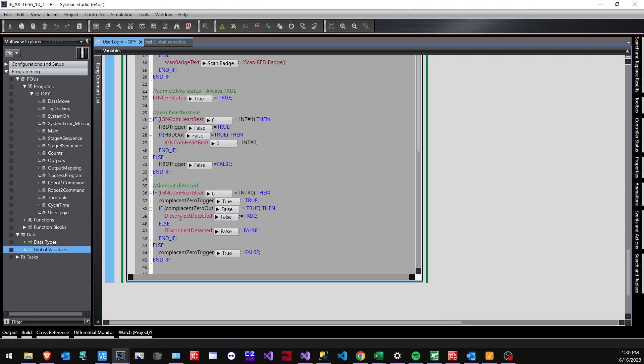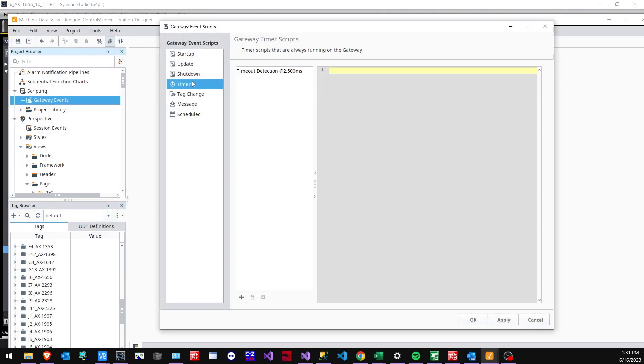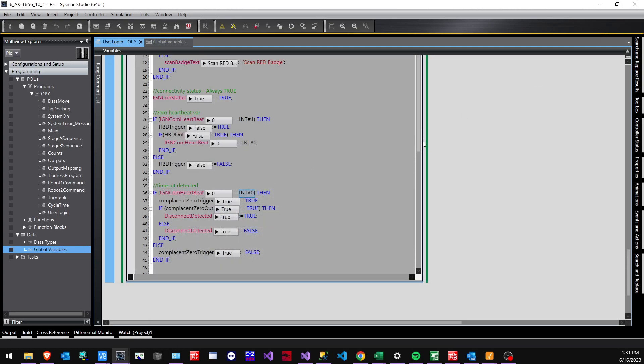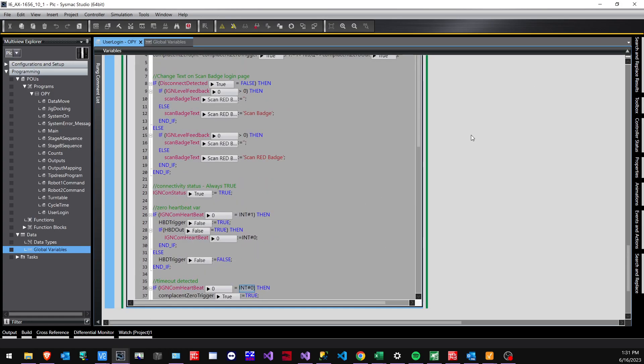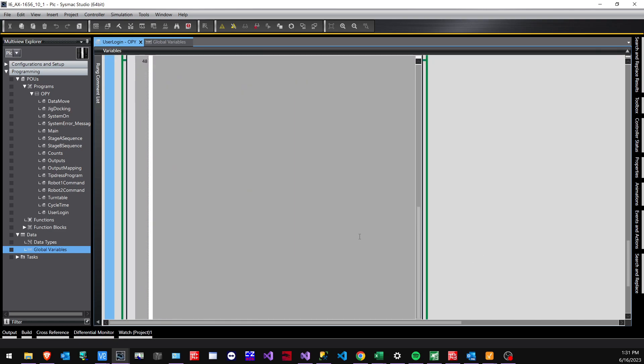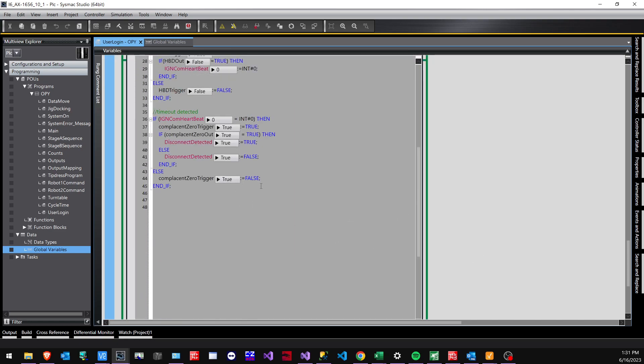In this code right here, the disconnect detected — as you can see — it turned to true. Basically, what this does is: if it's 0, meaning Ignition is not constantly pushing it to 1 every 2.5 seconds, then it's going to start the timer, which is set to 10 seconds. So after 10 seconds of it being 0 — meaning Ignition never actually turned it to 1 — disconnect detected turns true, and you can utilize this Boolean variable within your code however you'd like.